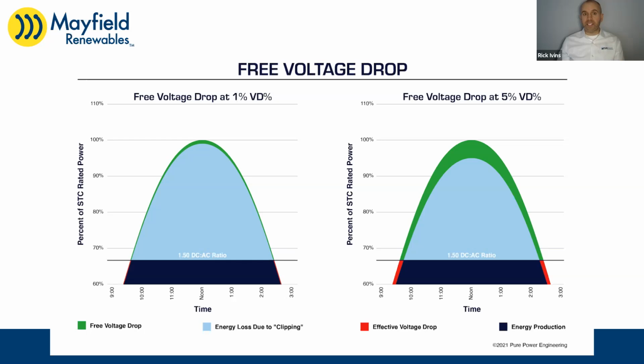You might spend a bunch of money because your contract says you have to be at 1% voltage drop. In this case, a lot of that benefit is gained on the left, below the clipping line on the shoulders at the start and end of the day before you're clipping. On the right, at 5% voltage drop, you can see the lines in red a bit better -- you still have voltage drop when you're not clipping, and it's a bit more. But the higher the DC to AC ratio, the more frequently you'll be in that clipping area, and the more frequently this voltage drop becomes free and doesn't cost you anything.